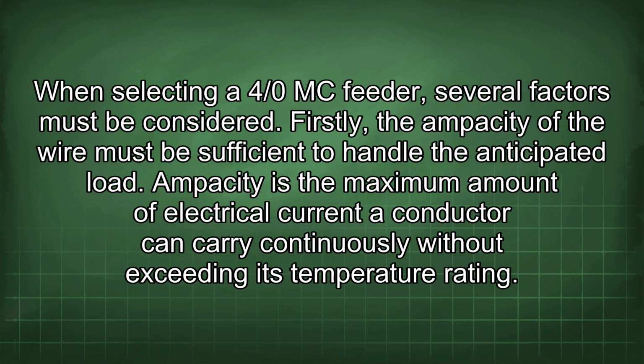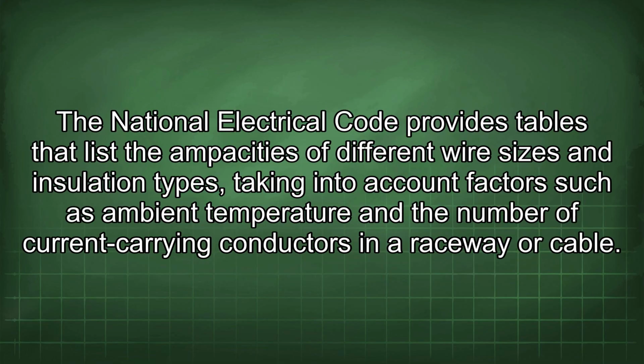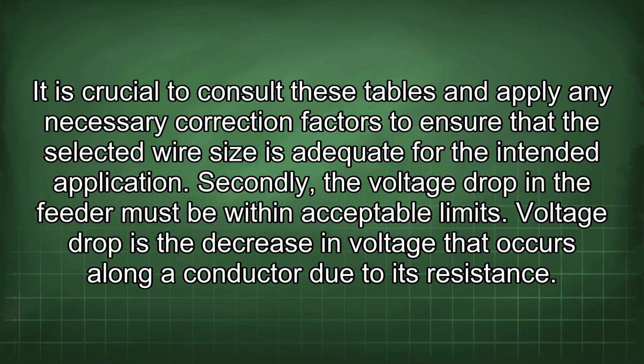safety and efficiency. When selecting a 4/0 MC feeder, several factors must be considered. Firstly, the ampacity of the wire must be sufficient to handle the anticipated load. Ampacity is the maximum amount of electrical current a conductor can carry continuously without exceeding its temperature rating. The National Electrical Code provides tables that list the ampacities of different wire sizes and insulation types, taking into account factors such as ambient temperature and the number of current-carrying conductors in a raceway or cable. It is crucial to consult these tables and apply any necessary correction factors to ensure that the selected wire size is adequate for the intended application.